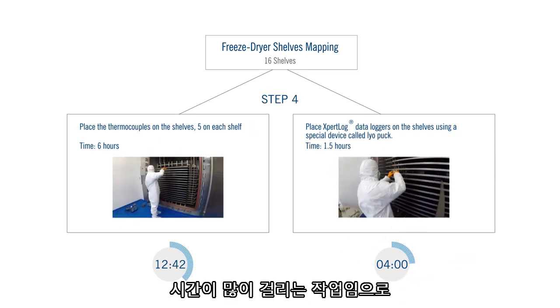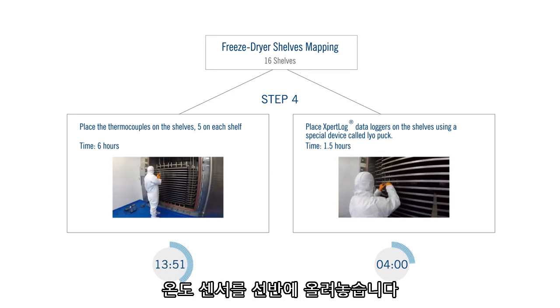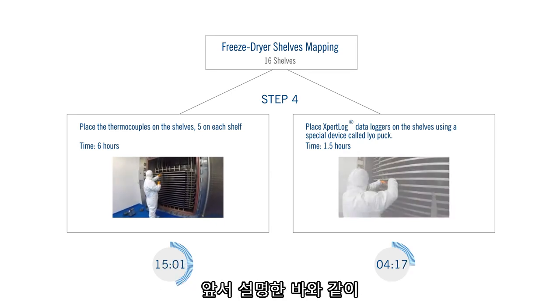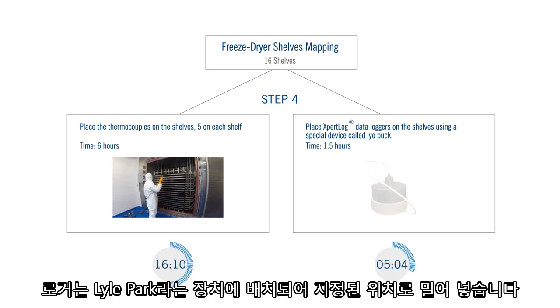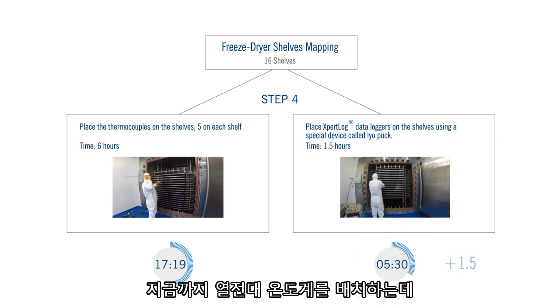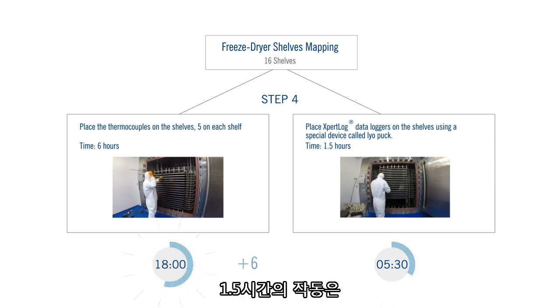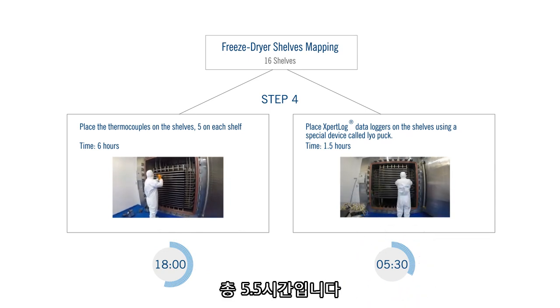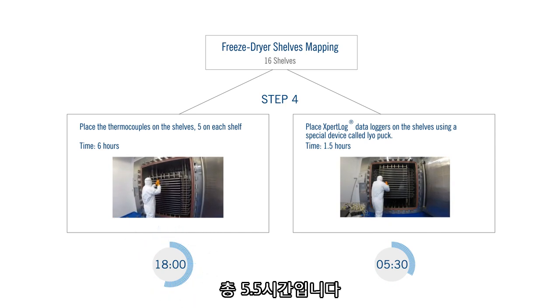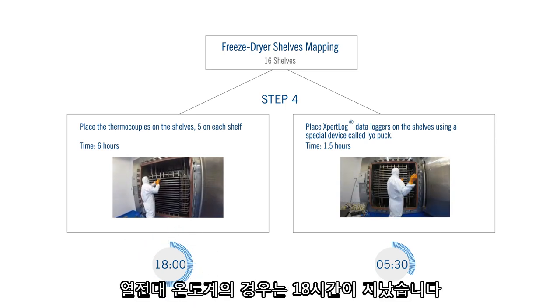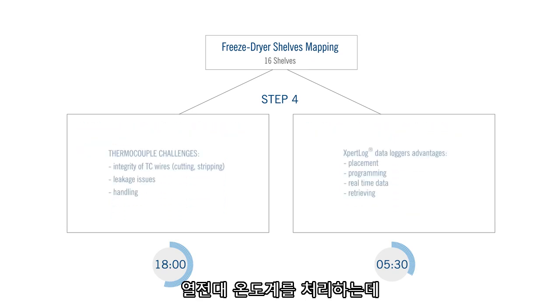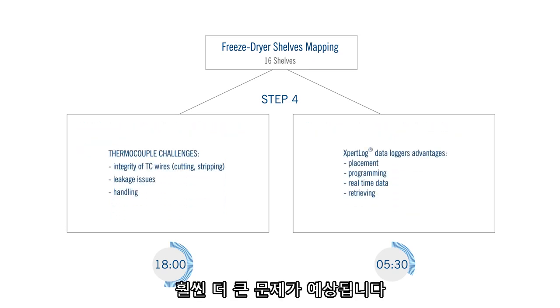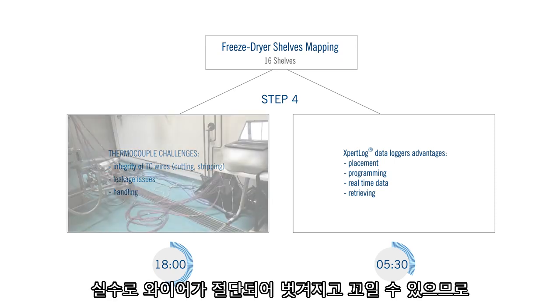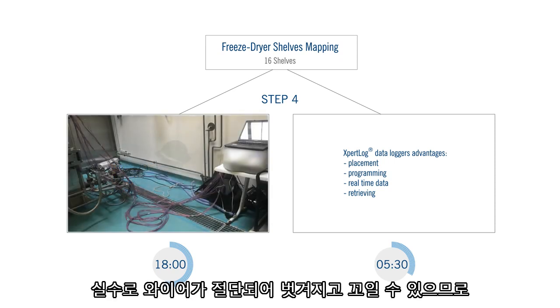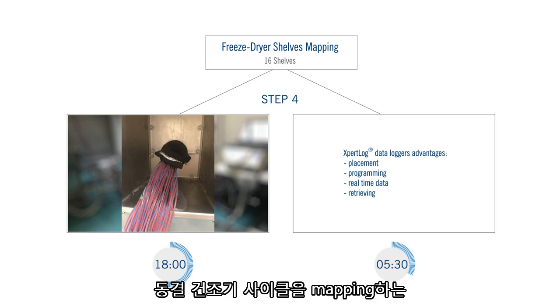A time-consuming operation is placing the temperature sensors on the shelves as previously described. The loggers are placed in a device called LyoPuck and pushed to the designated location. A 1.5 hours operation compared to a lengthy 6 hours to place 80 thermocouples. So far, a total of 5.5 hours for data loggers versus 18 hours for thermocouples. Guess who the winner is again? Notwithstanding the time required to handle the thermocouples during the mapping, even bigger challenges are to be anticipated when using them. The wires may be accidentally cut, stripped, twisted, which increases the total time and cost of the mapping.